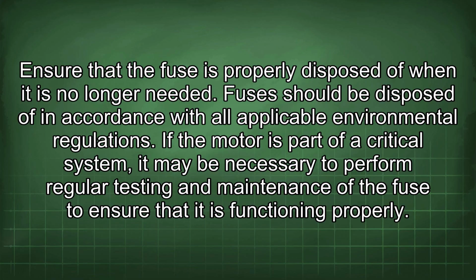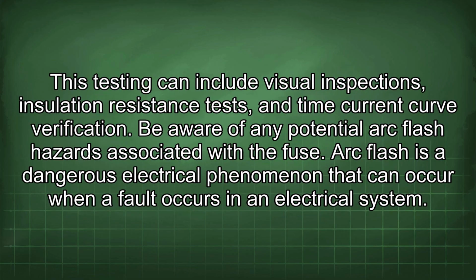If the motor is part of a critical system, it may be necessary to perform regular testing and maintenance of the fuse to ensure that it is functioning properly. This testing can include visual inspections, insulation resistance tests, and time current curve verification.